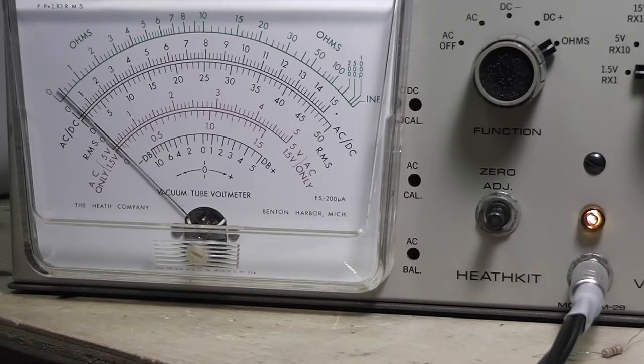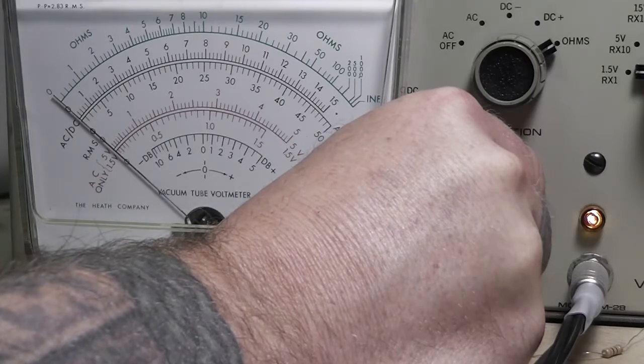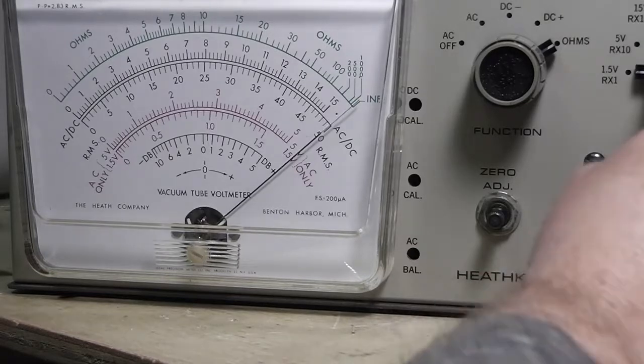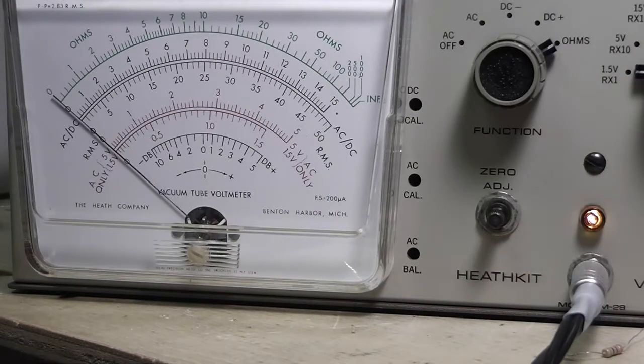Okay. Now you see that and you think something's wrong with it. No, what it's doing is reading the resistance in these leads. Right now we're reading about 0.3 ohms, and that's about typical when you have lead resistance. But what you can do to null that out is put your test leads together and bring it down to 0. Then take them loose, grab your ohms adjustment, and bring it back up to infinity. Now this should go back to 0. What you've done is nulled out the resistance in these wires.